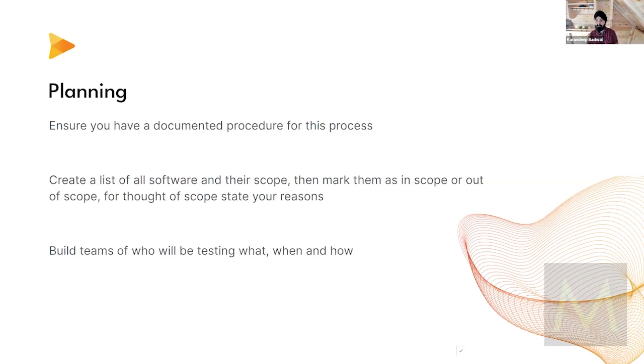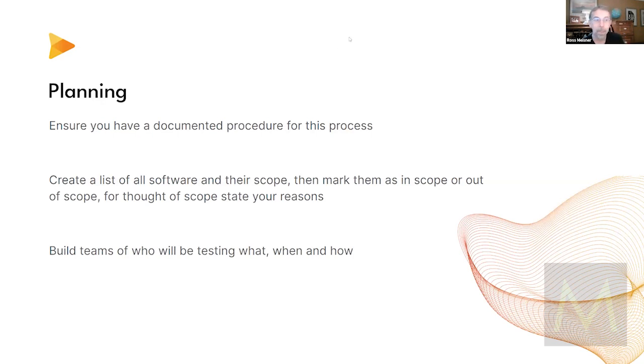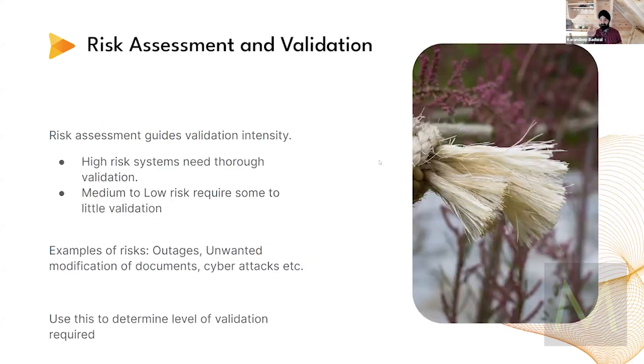Ross asks: how deep do you go? If software uses Google or AWS tools, which use public domain modules, which use programming — how deep are you responsible for going? Karandeep says he's coming on to that in the next few slides. Moving on to risk assessment: high risk systems need a thorough validation and we need to dig deep. Medium to low risk require some to little validation.